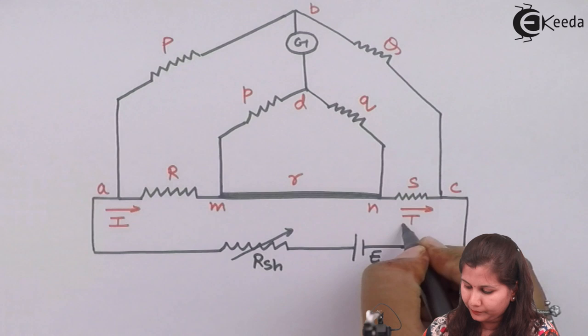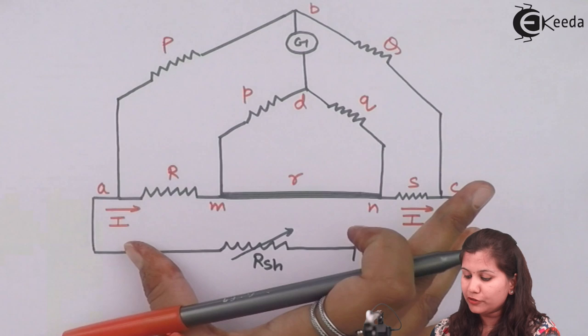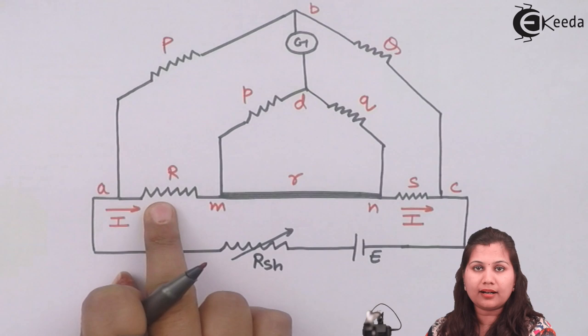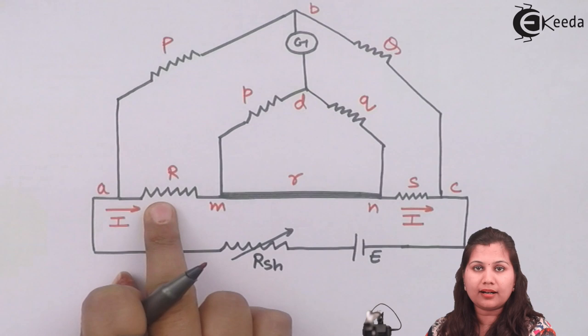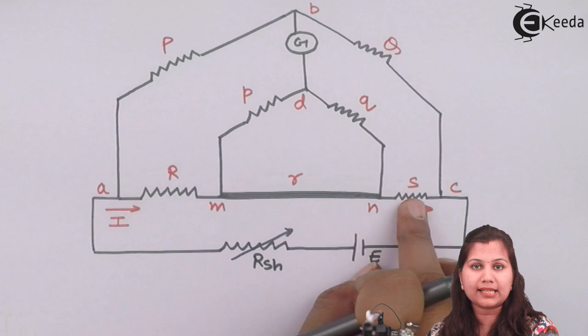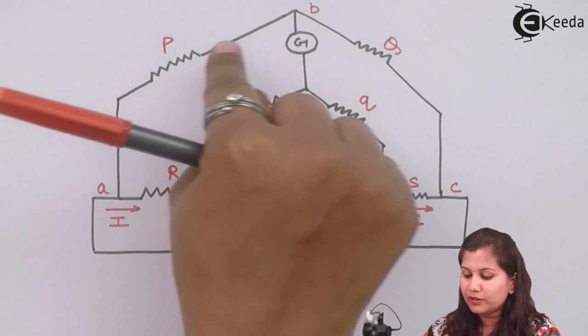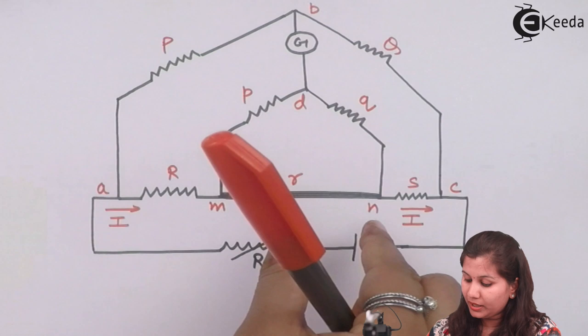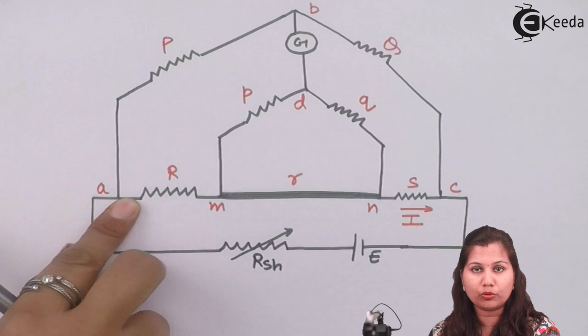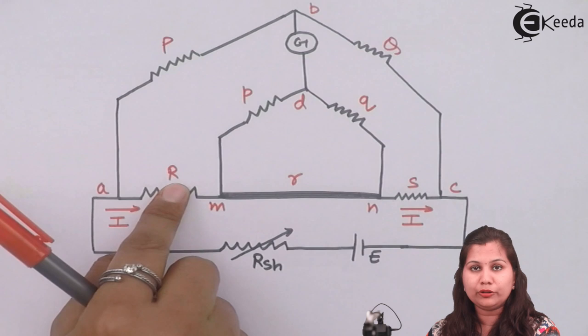This is the circuit diagram for the Kelvin double bridge. There are two ratio arms: one set P/Q and another set small p/small q, with the galvanometer connected between them. R is the unknown resistance and S is the standard resistance, just like in the Wheatstone bridge. Small r is the resistance of the connecting lead connecting the unknown resistance to the standard resistance.